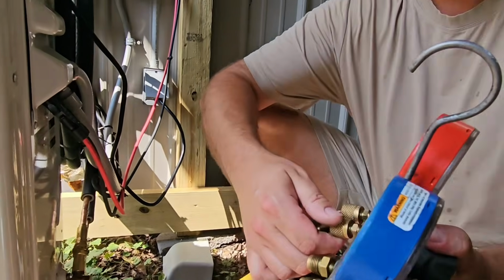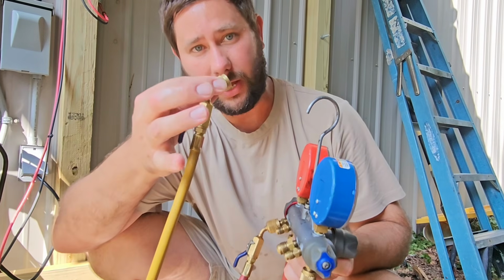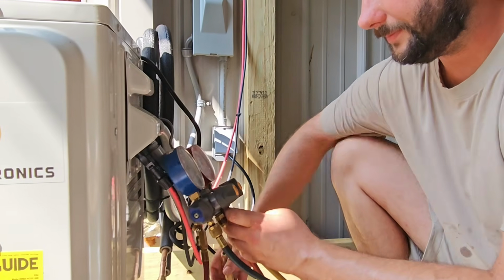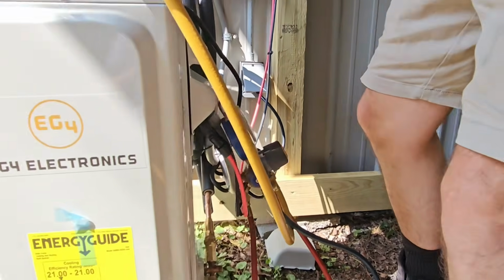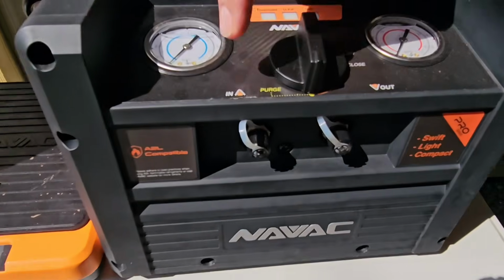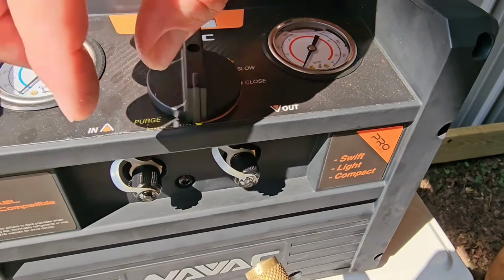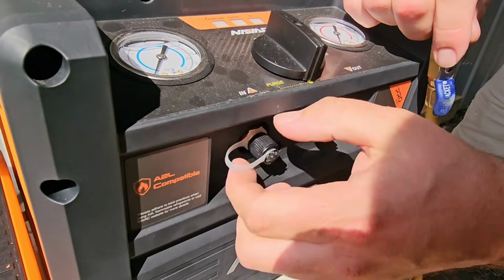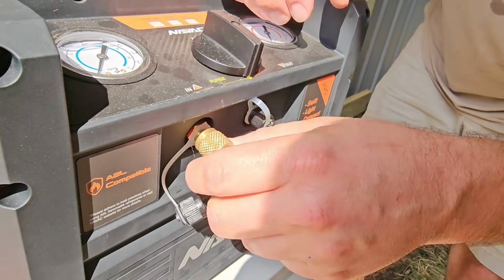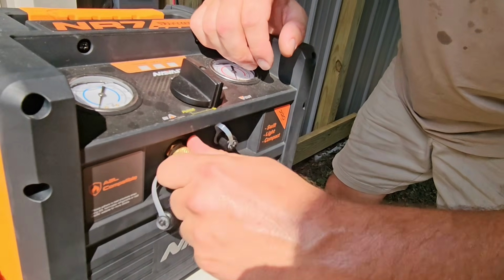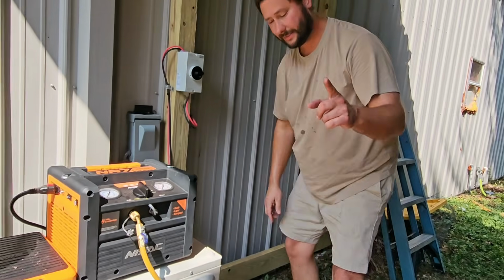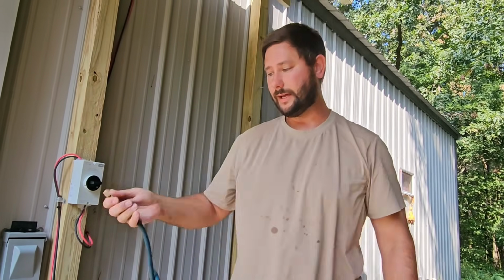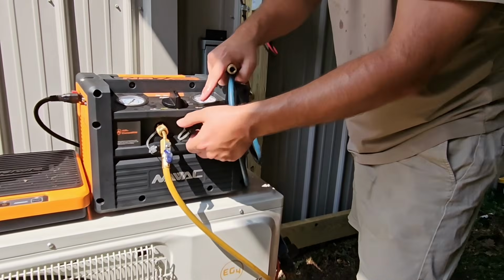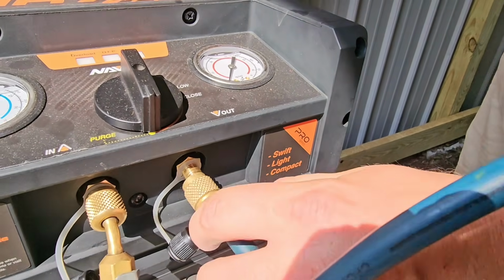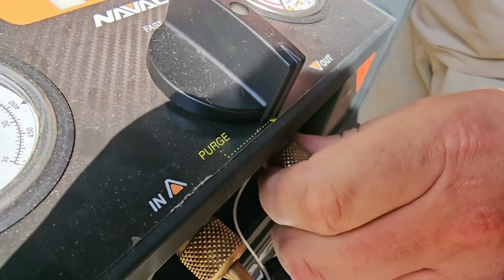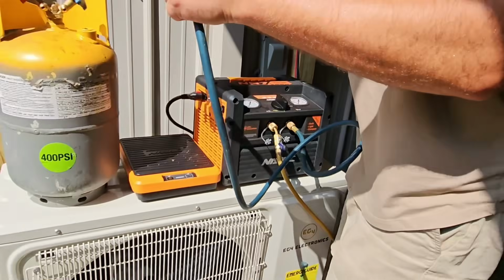Now what we're going to do is take the yellow hose off of the manifold, and then hook it to our recovery machine. You'll notice on the recovery machine there's an in and there's an out. We're going to go in. So we're going to take the cap off of the port that's labeled in, and connect our yellow hose fitting straight to it. Once that's connected, we need one more hose. We're going to hook it to our outlet port. See where it says out? Now we're going to connect this here, and then connect the other side to our recovery tank.